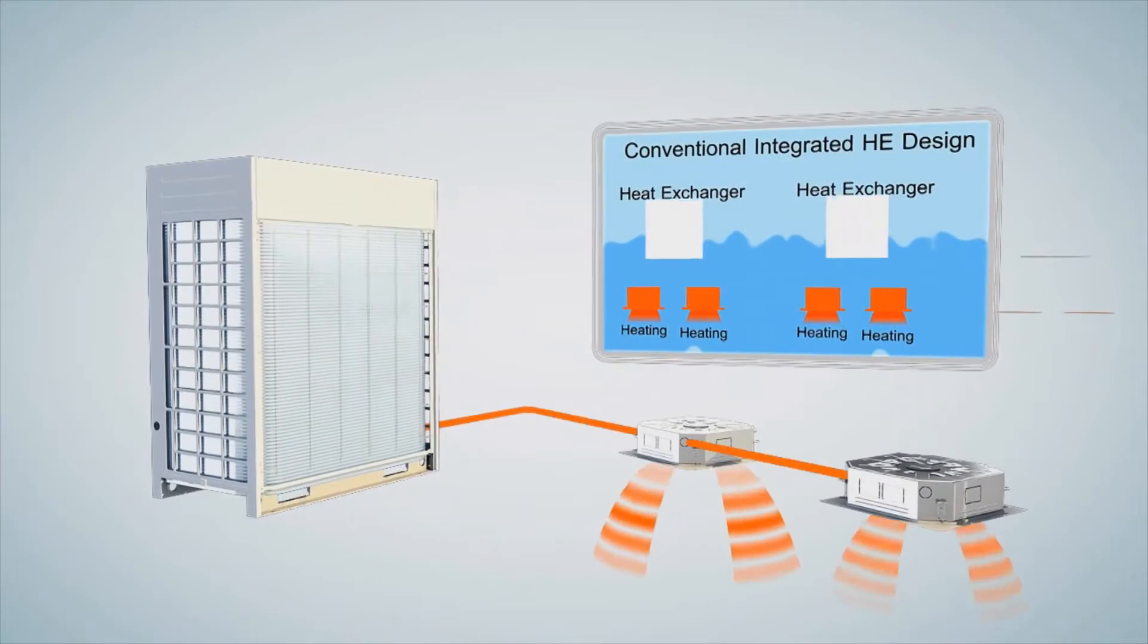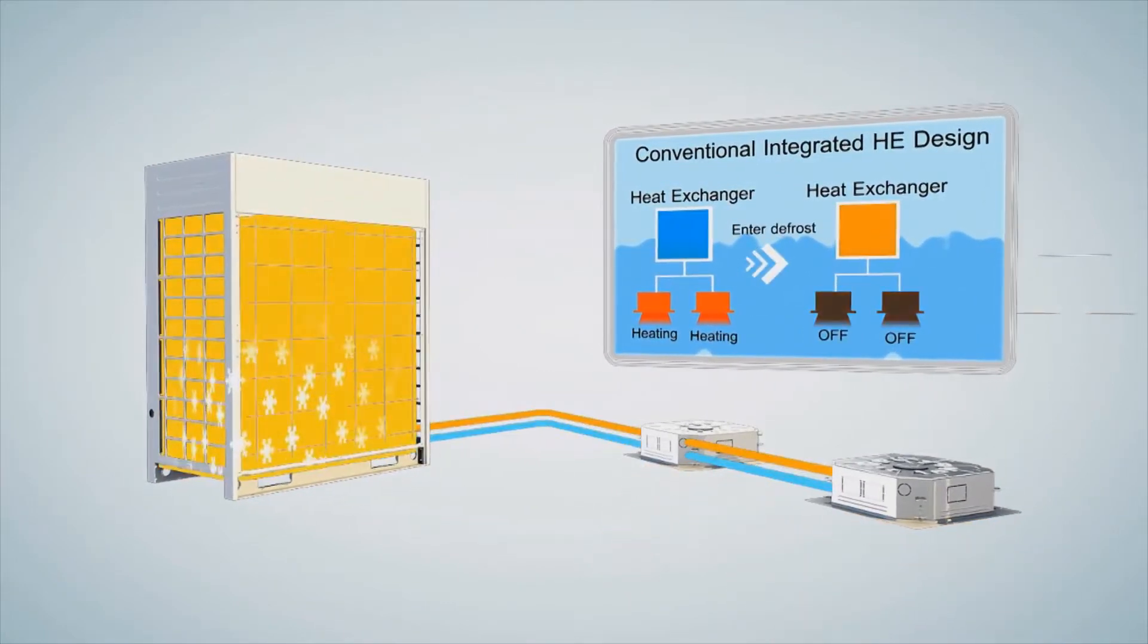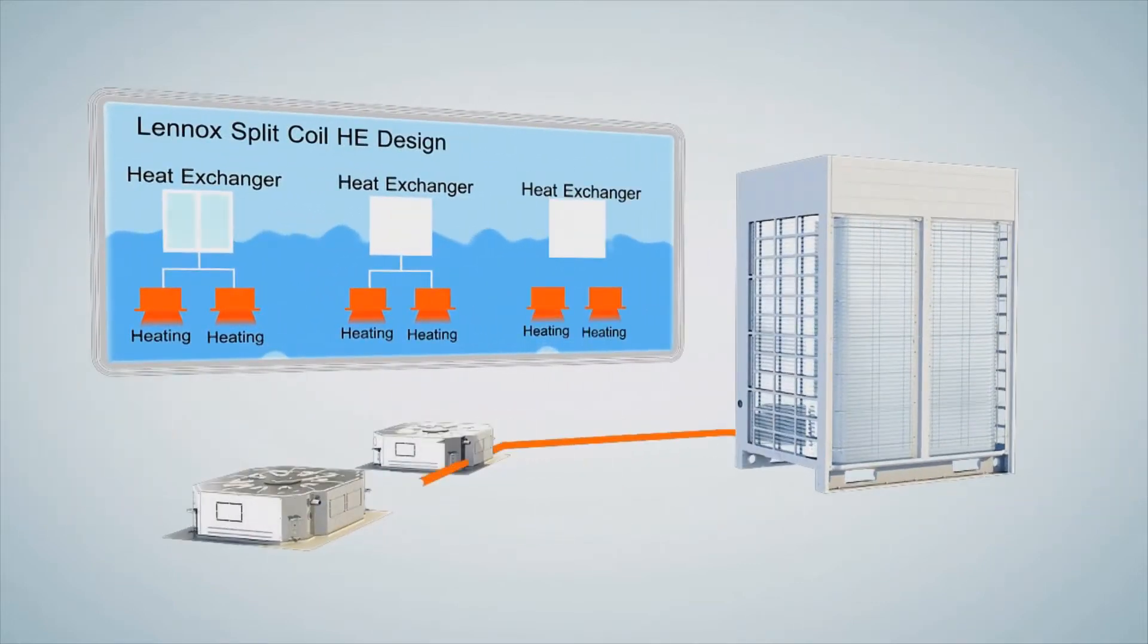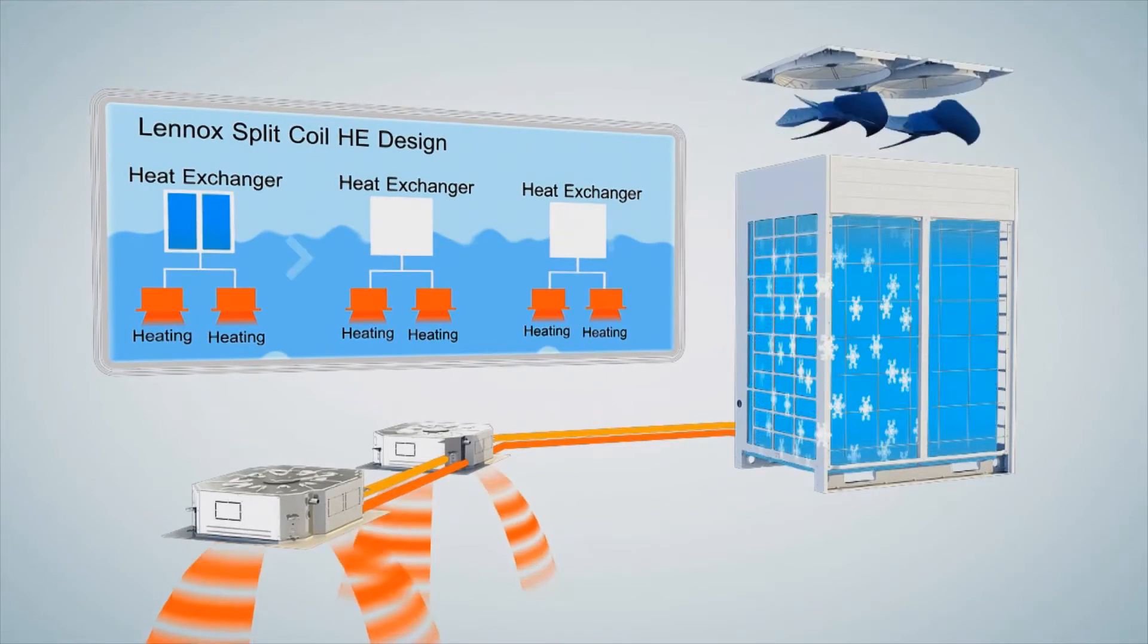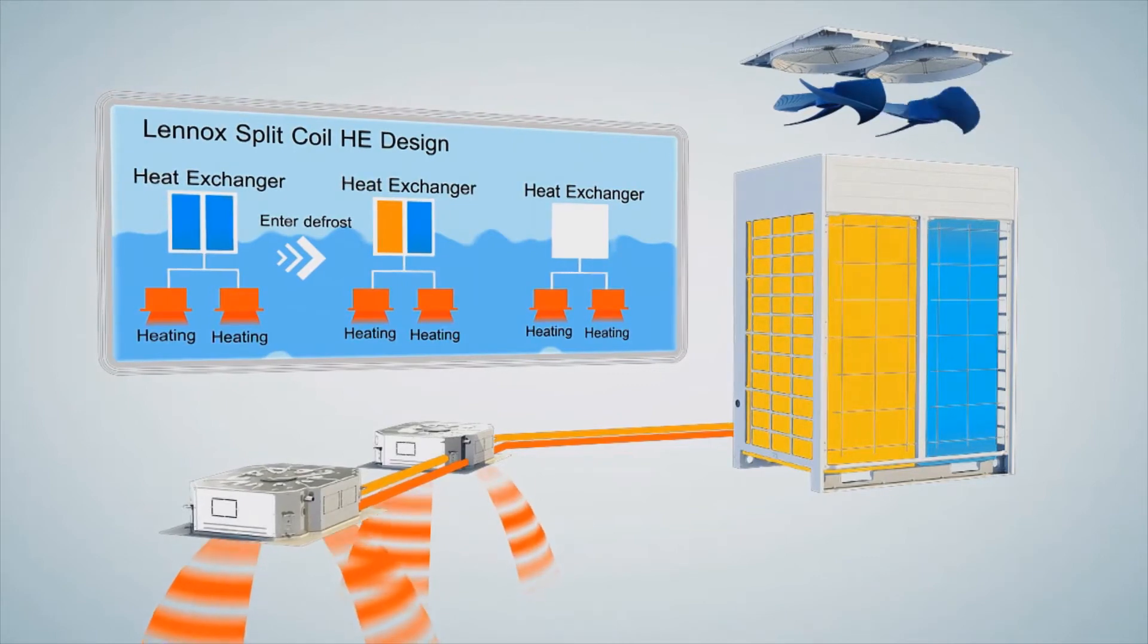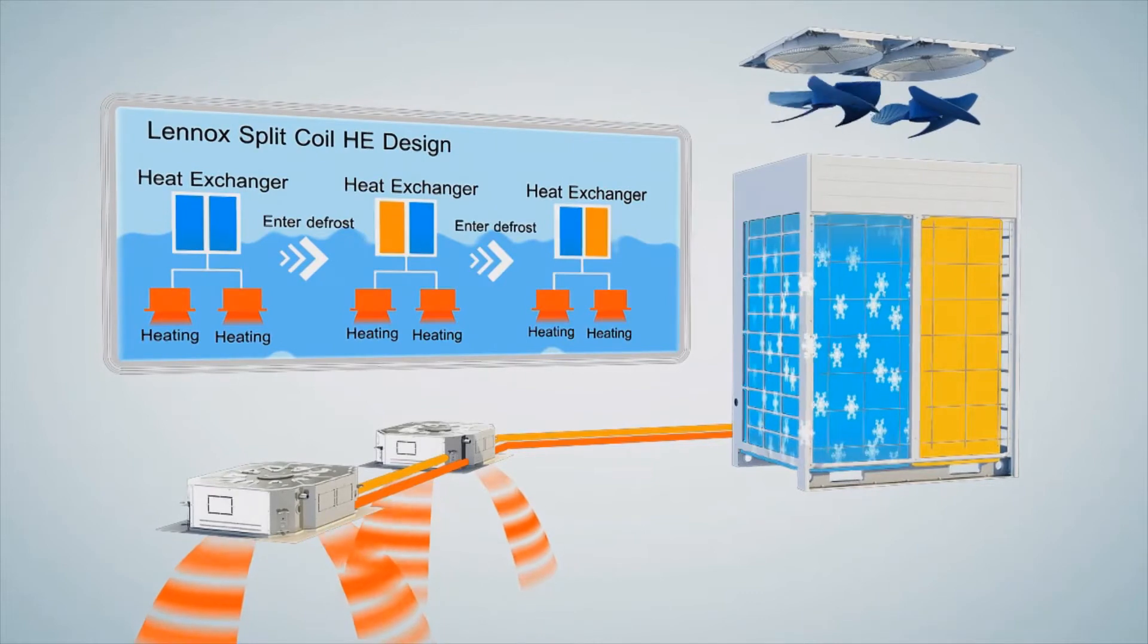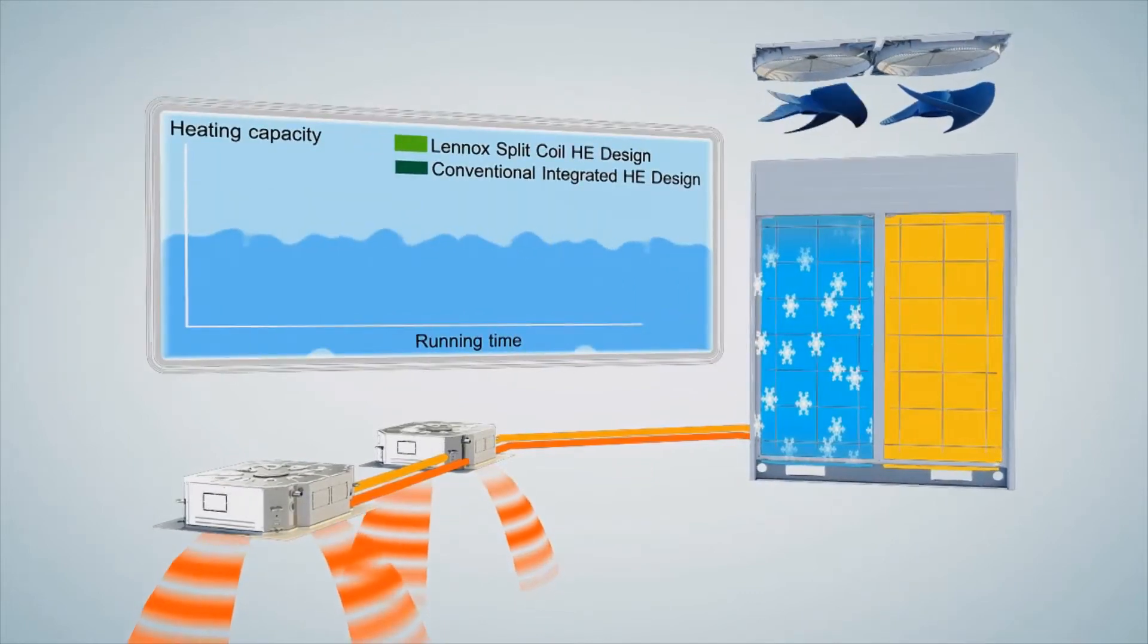A conventional integrated heat exchanger working in defrost mode must stop indoor unit operation. The Lennox VRF system utilizes a uniquely designed split coil heat exchanger and independently controlled fan motors to allow the system to continuously deliver heating throughout the defrost cycle. One portion of the coil is defrosted separately while the other portion remains in heating mode.